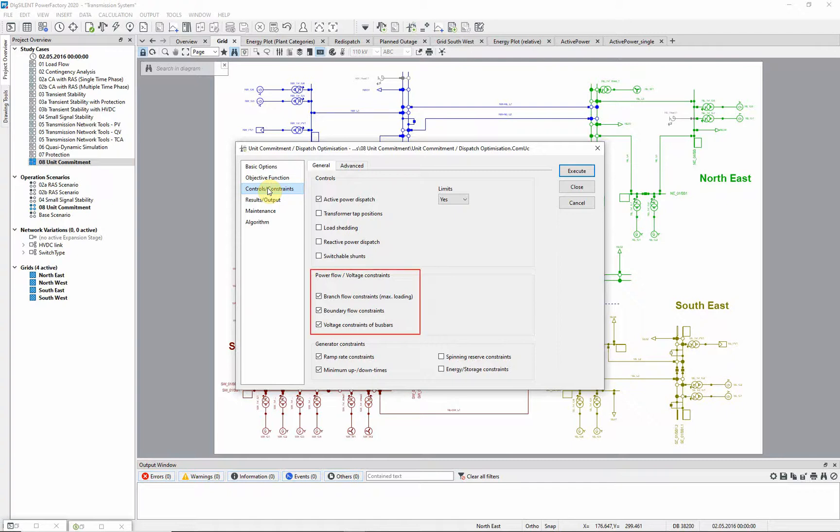In this example, we are considering branch flow constraints which are set to a loading value of 100% for lines and transformers, and voltage constraints for main busbars with a range between 0.95 and 1.05 per unit.